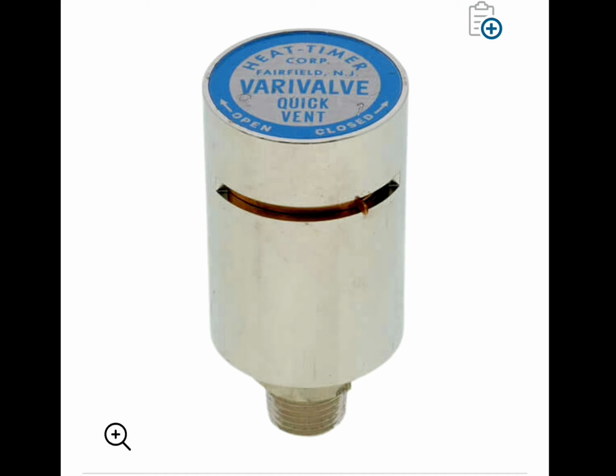And listen, just to give you a quick story. I lived in a house years ago, and the first thing, I had this same vent on my radiator, which is a self-standing cast iron radiator. All the radiators were cast iron. The living room radiator, however, had problems where return water would get inside of it, and eventually at some point the radiator would fill up and it was just spraying out water. Now look at the size of this opening.